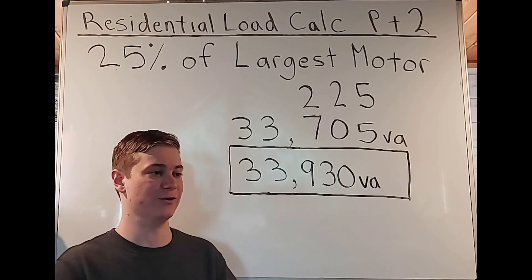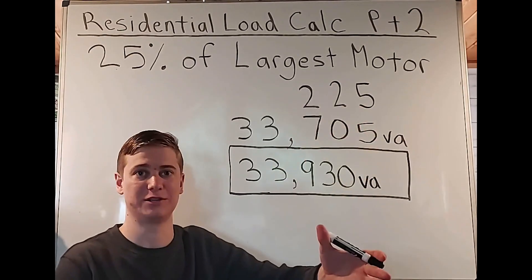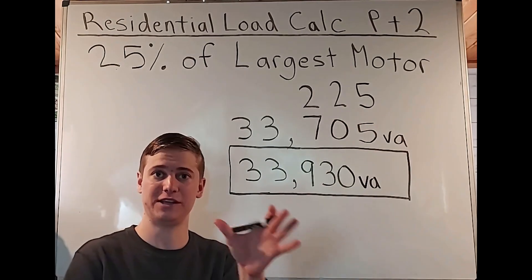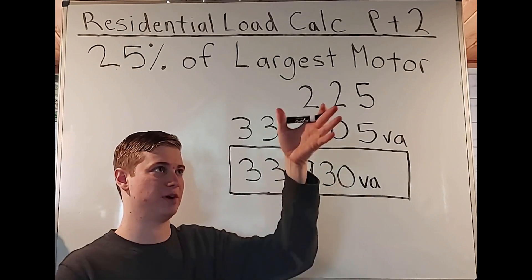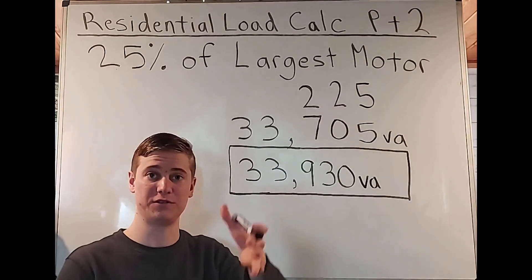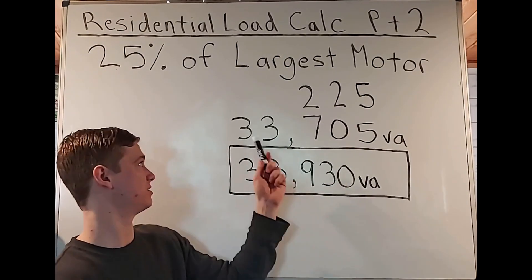But in all reality, it's pretty simple. You just got to know that after you do everything else in your load calculation, at the very end is how I do it, because there's all the demand factors and stuff. I just look at what is my largest motor, and I take 25% of that, and I add that to the rest of the load.